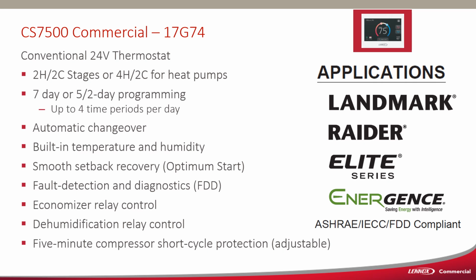We also have the ComfortSense 7500. This is another conventional 24-volt thermostat, 2-stage heat, 2-stage cool, 4-stage heat if you have a heat pump. 7-day programmable up to 4 time periods per day. It has automatic changeover from heating to cooling, built-in temperature and humidity sensors, smooth setback recovery option, fault detection and diagnostics, economizer relay control outputs, and a dehumidification relay control, which means you can use this on the Landmark with the Humiditrol hot gas reheat, and 5-minute compressor short cycle protection.